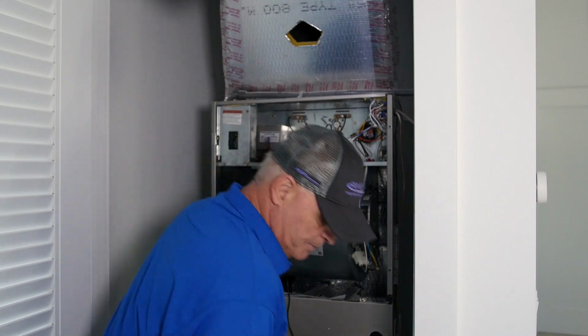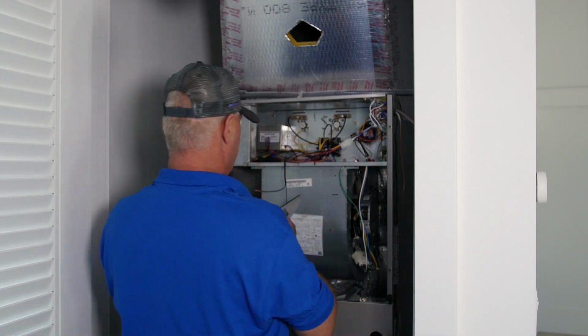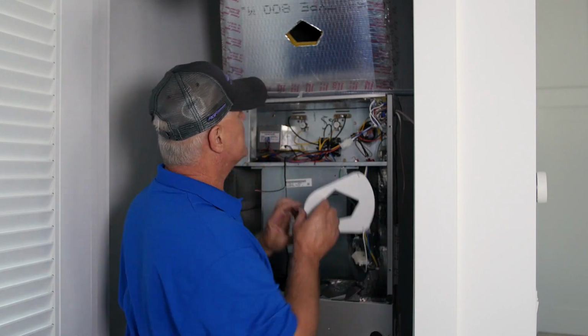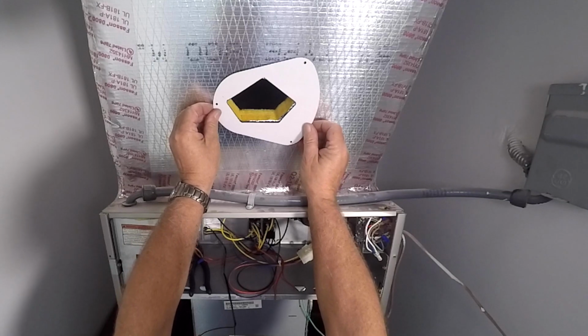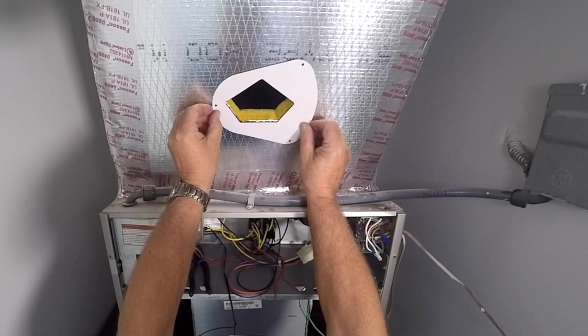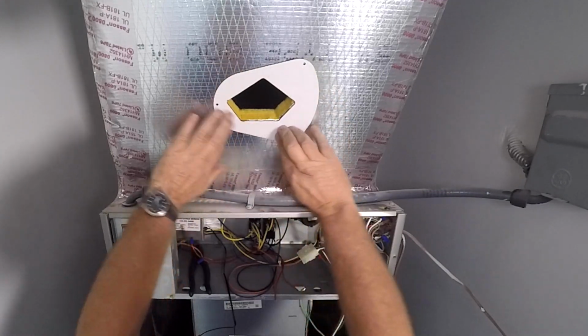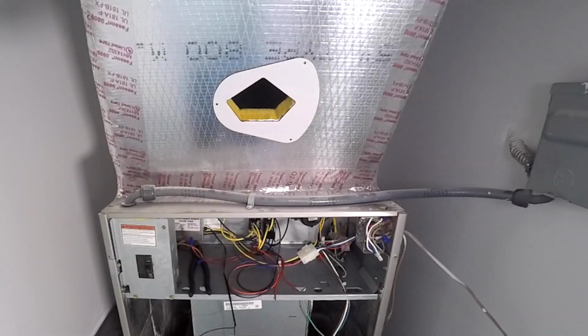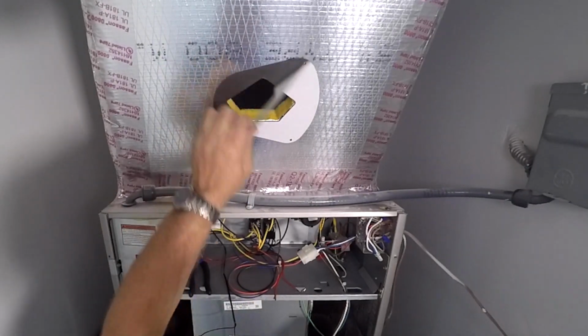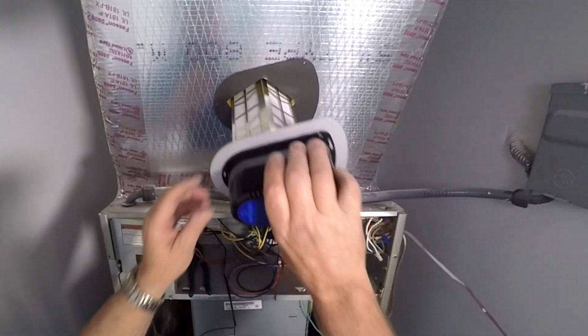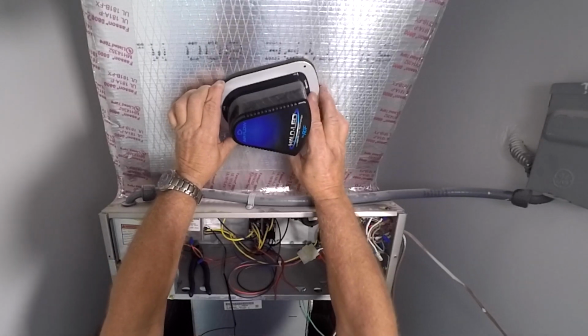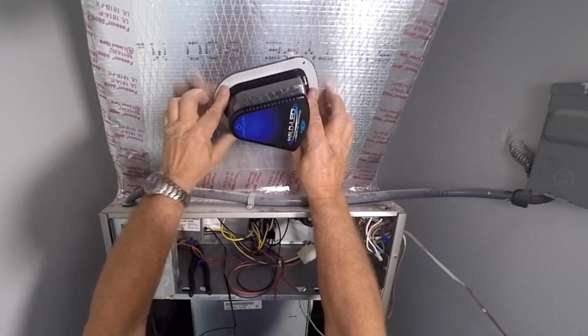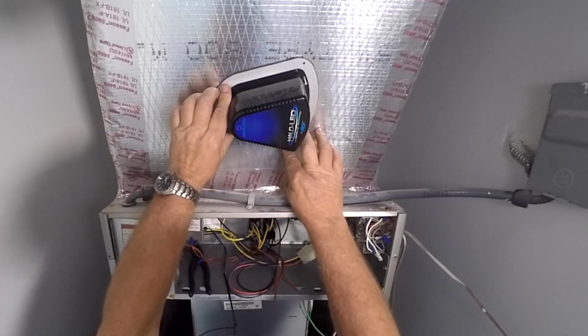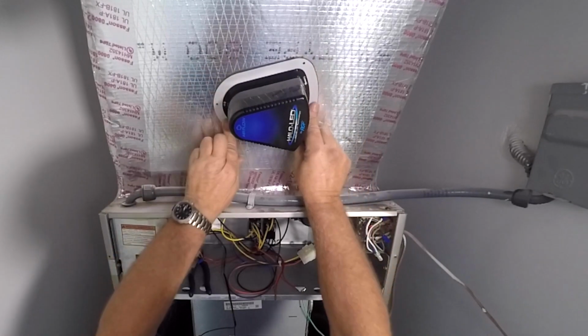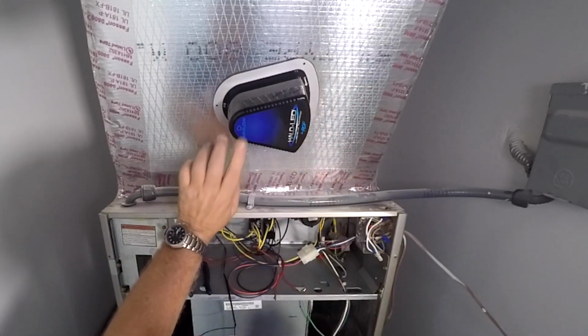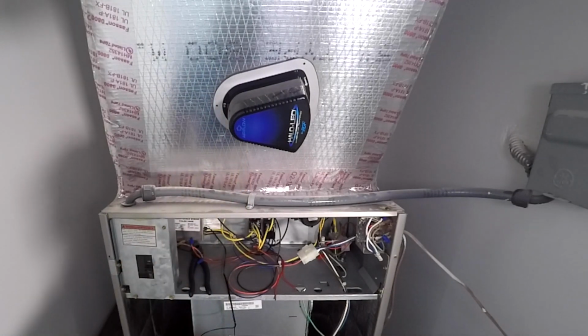Now that we have our hole cut, we're going to take our gasket, peel the tape from one side of it, and position it over our hole in the ductwork. And then, once we have that positioned, we're going to peel the tape off it and install the REME in, lining it all up with the gasket, and again making sure your airflow direction is up on this particular unit. Obviously, if your airflow is to the side or a downflow unit, you're going to have your arrow corresponding to the direction you are going.